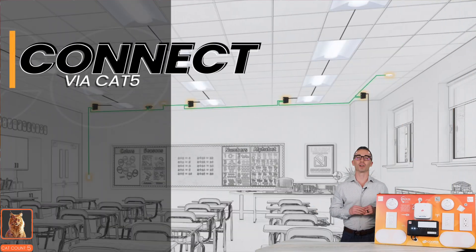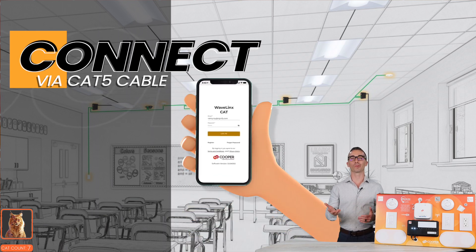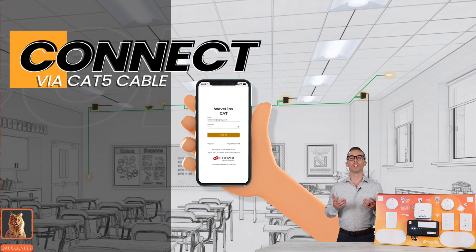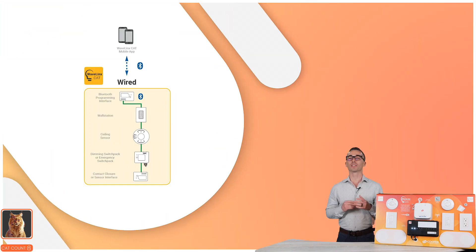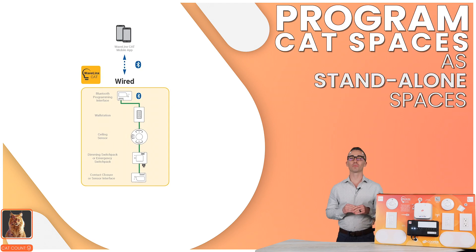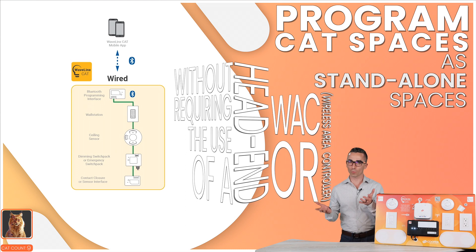All devices within the WaveLinx Cat brand connect via a Cat5 cable. You can utilize the Cat app to program Cat devices to a single room using the Bluetooth interface device that you connect at some point on a single run of these devices. This allows you to program Cat spaces as completely standalone without requiring the use of a head-end WAC or wireless area controller.